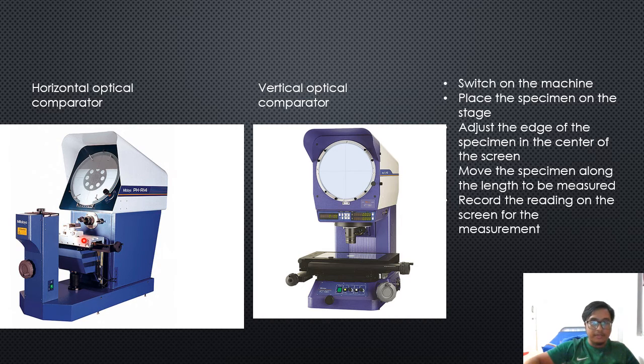There is a clamp here where we can put the specimen on the machine. For the horizontal optical comparator, we clamp the specimen to the machine, then set the edge of the side that we need to measure on the center of the screen. Then we move along the specimen edge until the final edge that we need to measure. A screen will then show the reading of the edge.